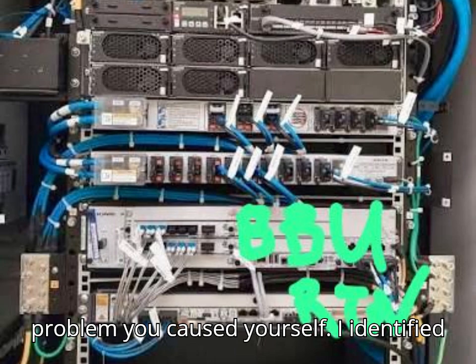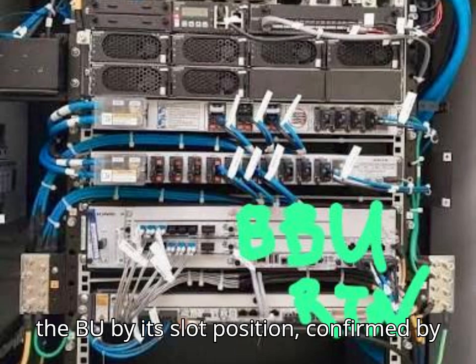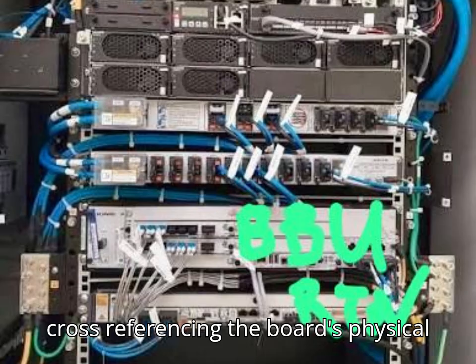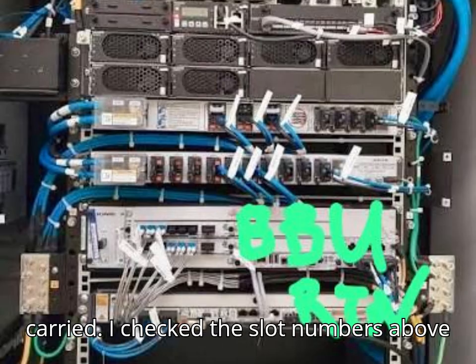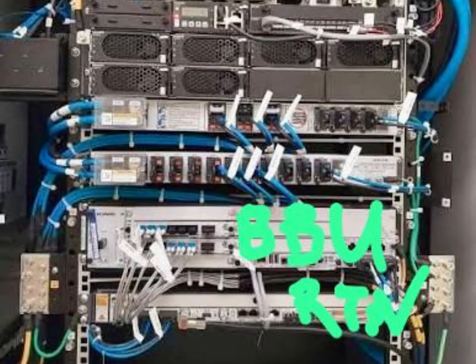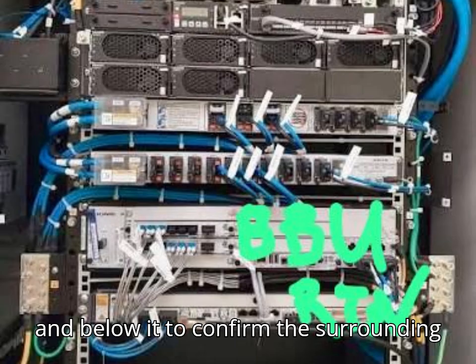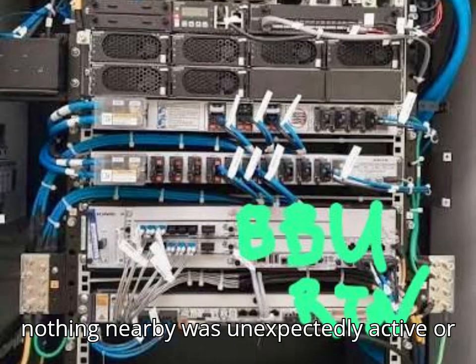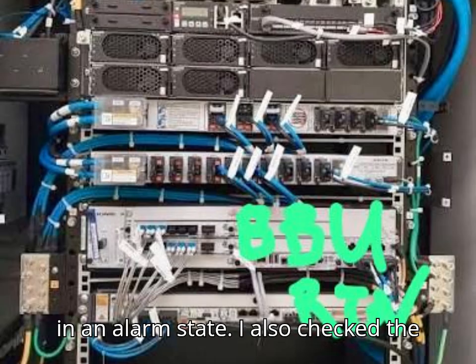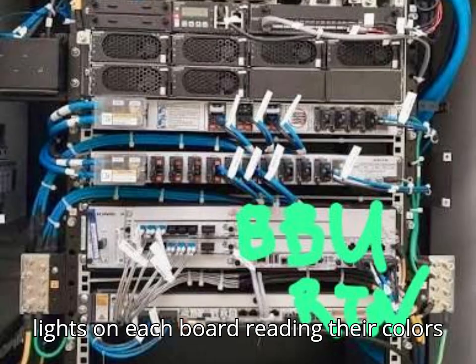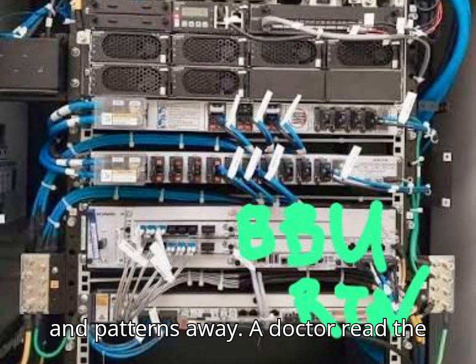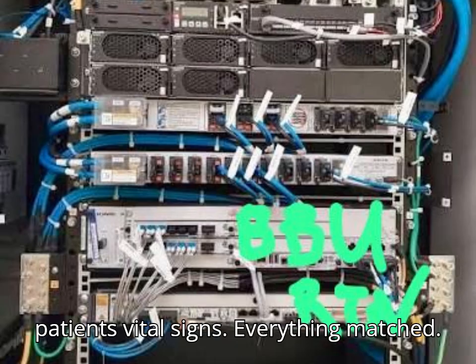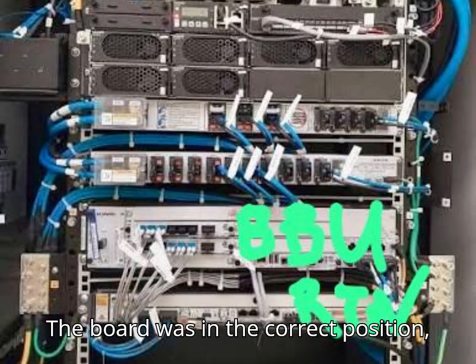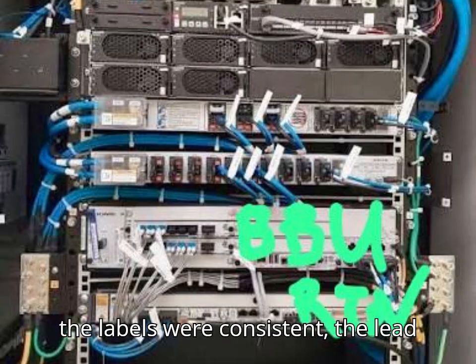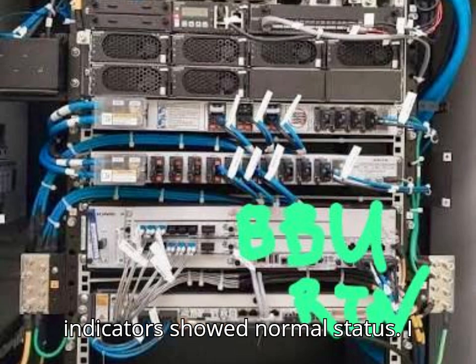I identified the BBU by its slot position, confirmed by cross-referencing the board's physical label against the site documentation I carried. I checked the slot numbers above and below it to confirm the surrounding hardware was correctly populated and that nothing nearby was unexpectedly active or in an alarm state. I also checked the faceplate indicators, the small LED lights on each board, reading their colors and patterns the way a doctor reads a patient's vital signs. Everything matched. The board was in the correct position. The labels were consistent. The LED indicators showed normal status.